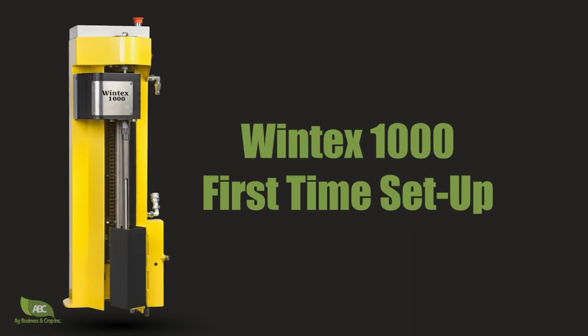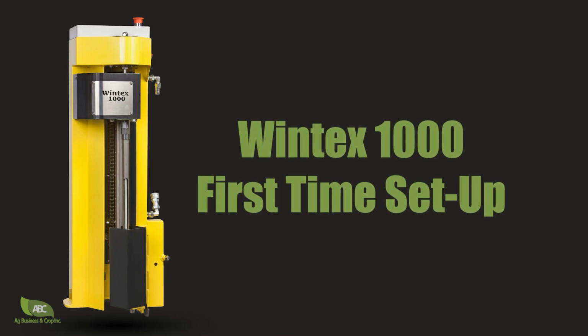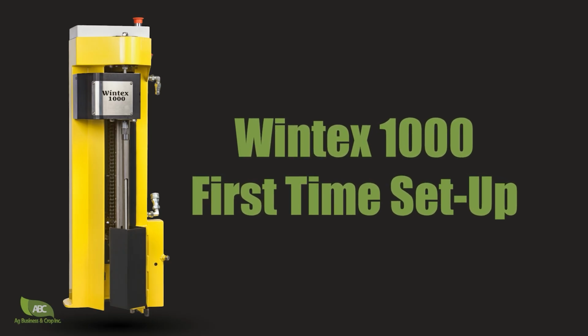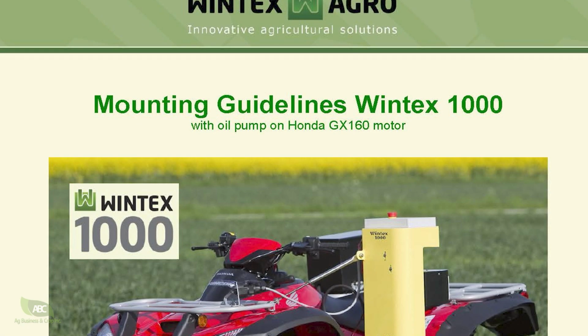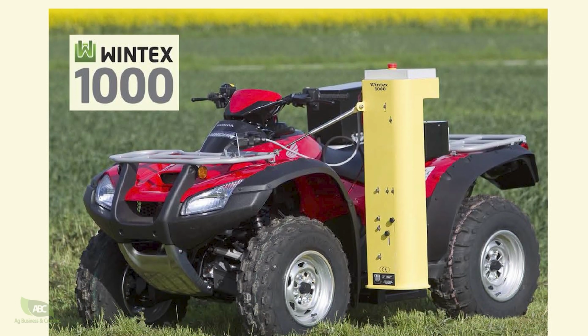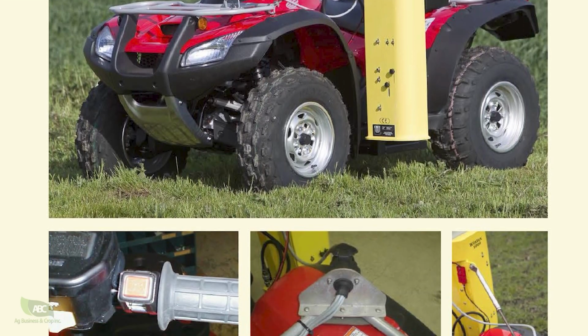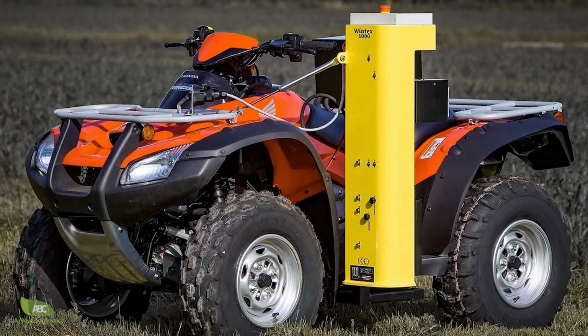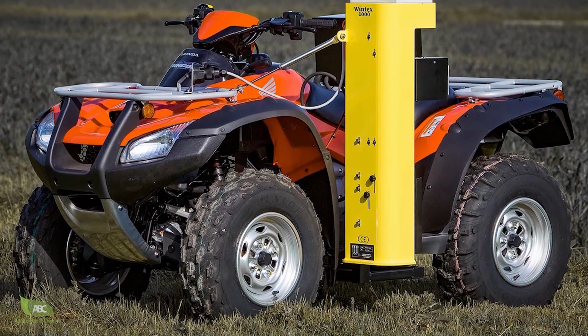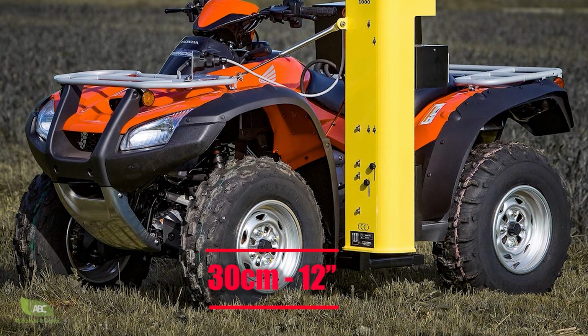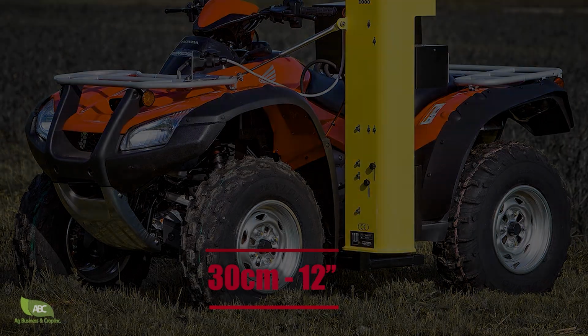In this video, we'll show you the most important points you need to check before running your W1000 for the first time. We are assuming that you read all the manuals and installed the machine properly, following all the instructions. Make sure the machine is not installed higher than 30 centimeters or 12 inches from the ground. You can measure it from the bottom of the yellow case to the ground.